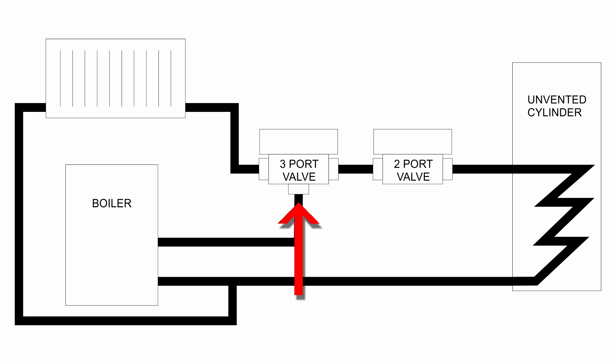One outlet goes to the radiators, just got one radiator shown there, and that returns to the boiler. And then the other outlet goes to the hot water cylinder, and again that returns to the boiler. So that's the sort of basic setup, and the two port valve actually goes, as shown here, on the outlet of the three port, so it's essentially between the three port valve outlet and the input to the cylinder.